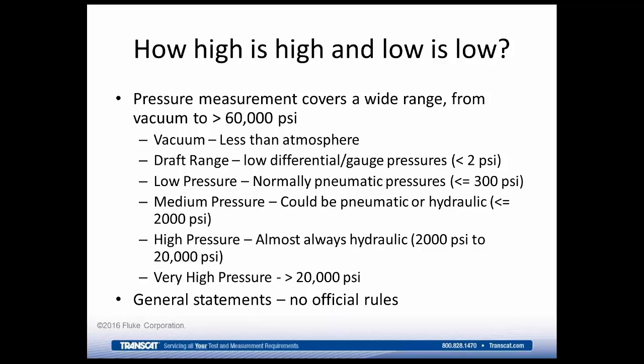Medium pressure, or excuse me, low pressure, are pressures that will normally use a pneumatic device to do the calibrations, oftentimes 300 psi or less. This is basically because that's a pressure that's easy to generate by hand with a pump. You are seeing that pressure range increase over time, but traditionally what we call low pressure or pneumatic pressures is in that 300 psi or so.